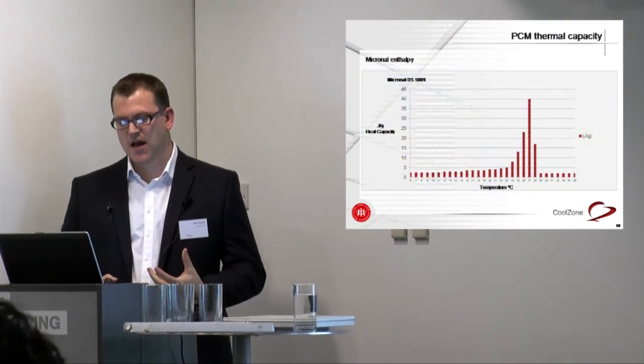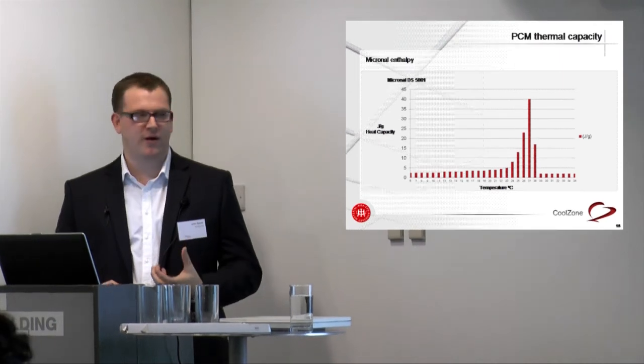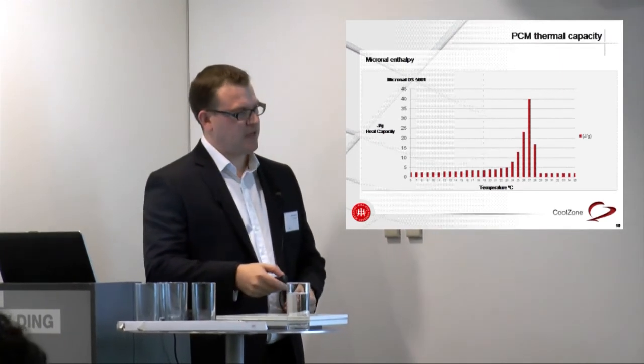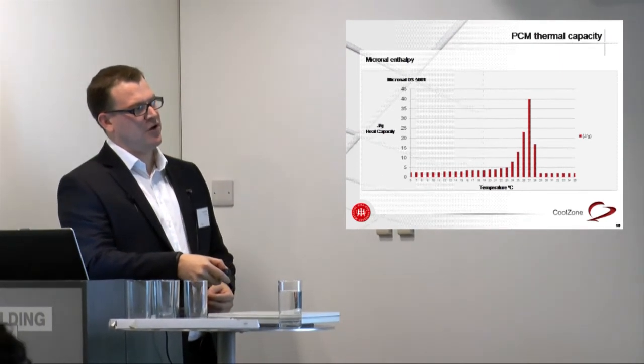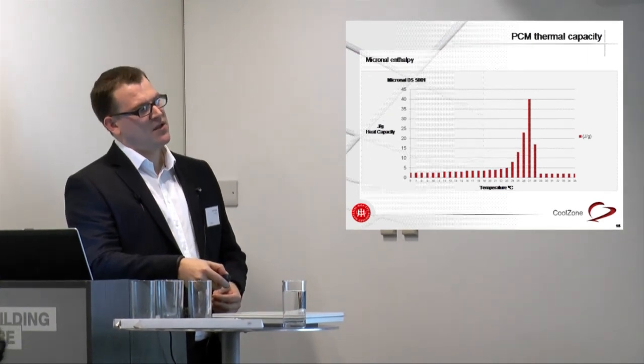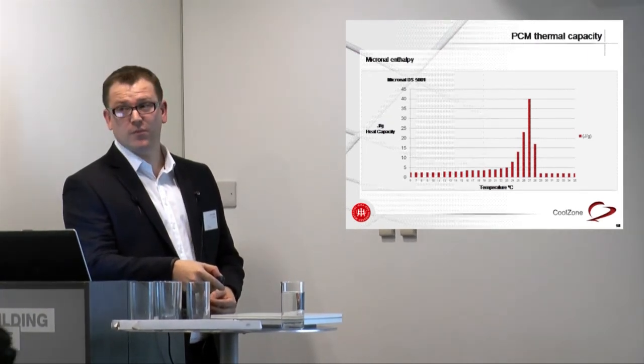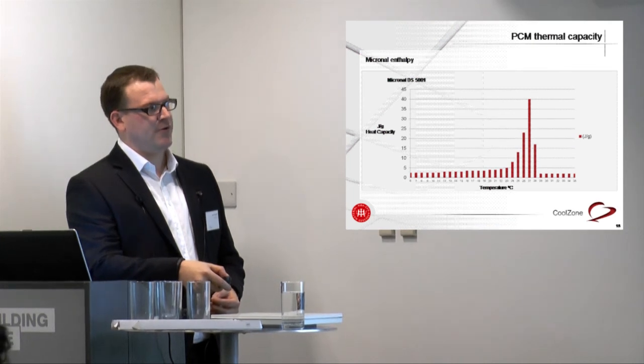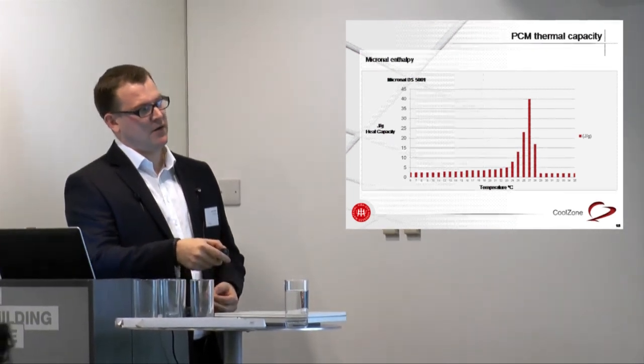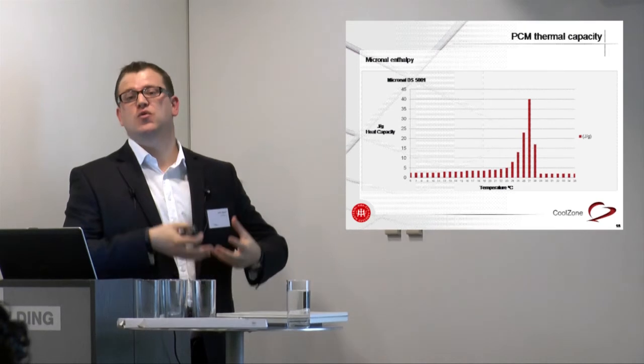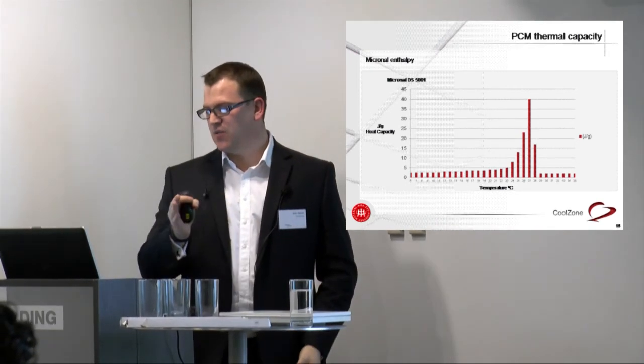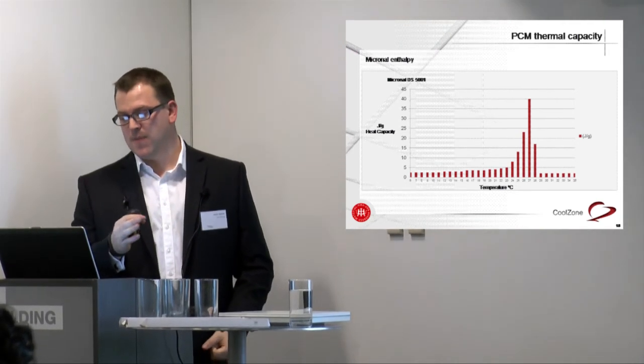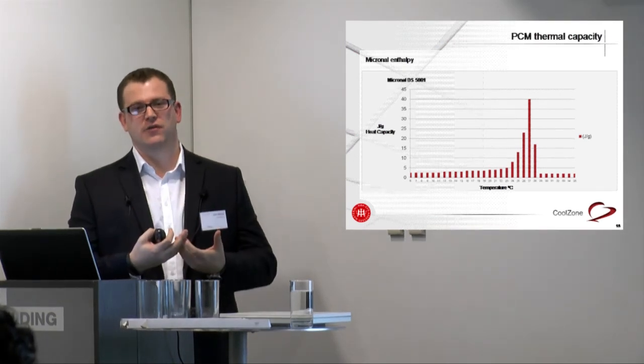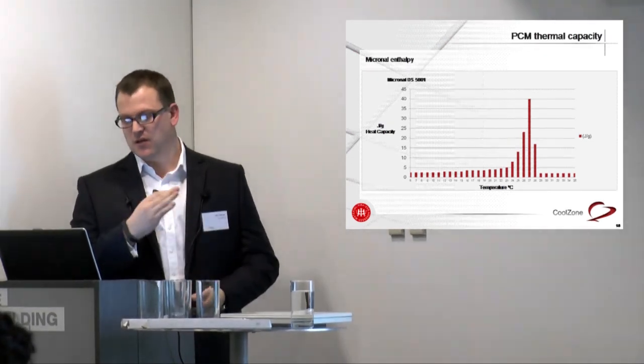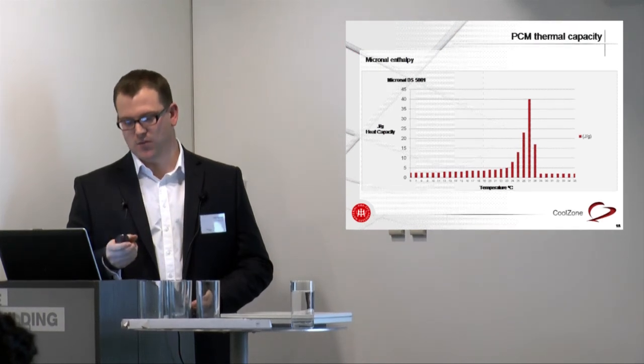This graph shows the enthalpy of PCM. As we go up the temperature scale, not a lot happens to the material. Then we suddenly reach 23 degrees, the melting point of the material, and there's a sudden spike, which is its ability to absorb that excess heat. Once we get past its useful temperature and the material is completely melted, there's not much storage capacity left.